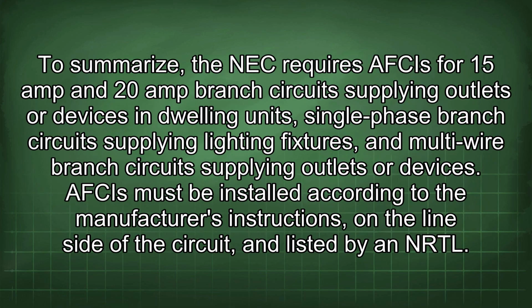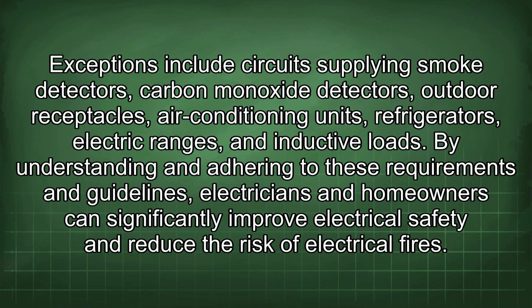To summarize, the NEC requires AFCIs for 15 amp and 20 amp branch circuits supplying outlets or devices in dwelling units, single-phase branch circuits supplying lighting fixtures, and multi-wire branch circuits supplying outlets or devices. AFCIs must be installed according to the manufacturer's instructions on the line side of the circuit and listed by an NRTL. Exceptions include circuits supplying smoke detectors, carbon monoxide detectors, outdoor receptacles, air conditioning units, refrigerators, electric ranges, and inductive loads.